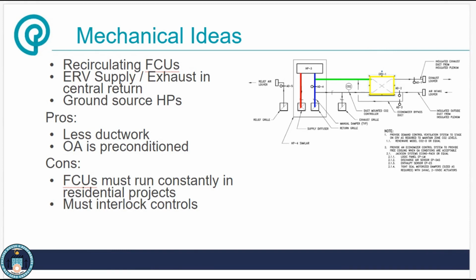It's less ductwork than having run a separate thing. You're preconditioning that outdoor air so it's not cold, and you can maybe back off on the recovery rate of an ERV a little bit. But again, if this were in a residential project, that fan coil would have to keep running consistently.